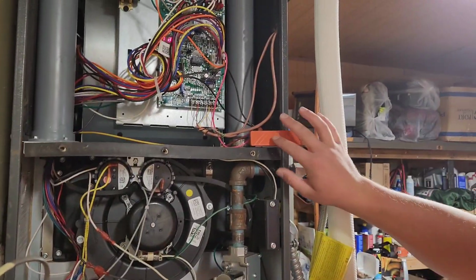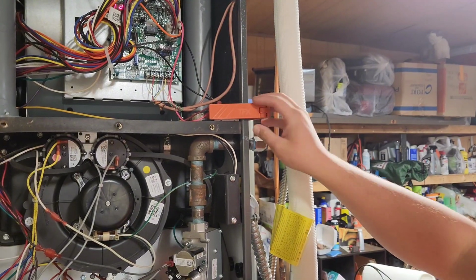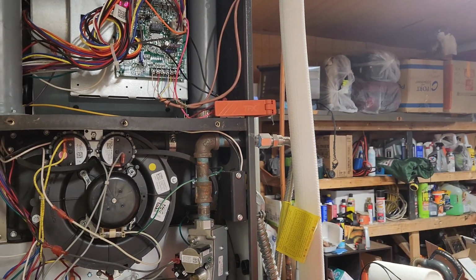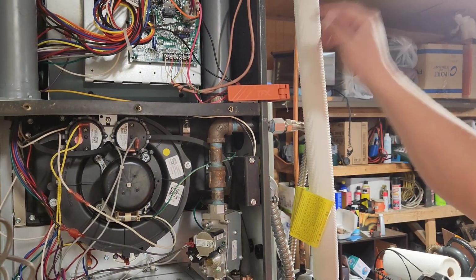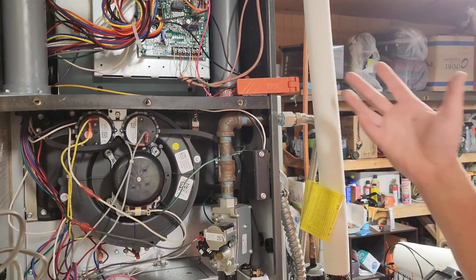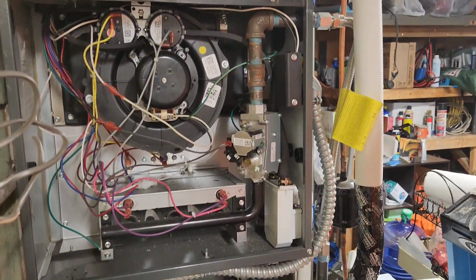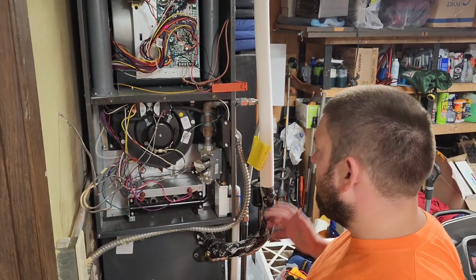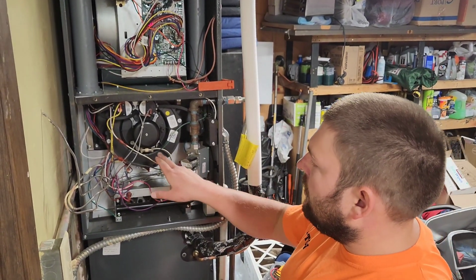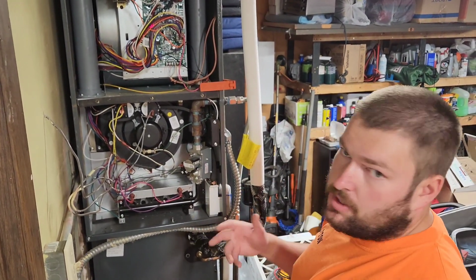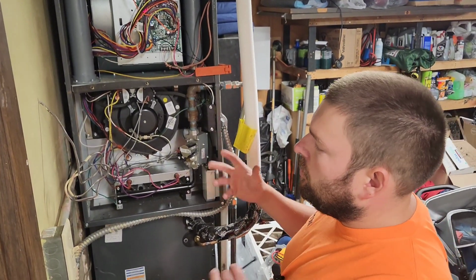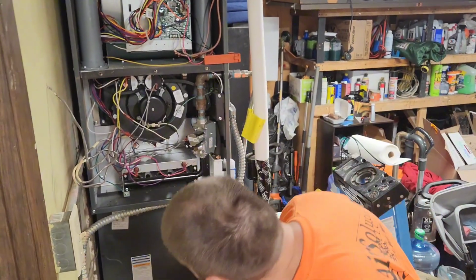Okay, so once we do everything inside the furnace, we'll put a door safety little magnet on here, or some guys will put a tape on there, just so that we have power to the furnace and we can actually see the sequence of operation when it starts. Okay, so we got heat on now. Your inducer motor's coming on. We're just watching the sequence of operation to make sure it's starting up properly.